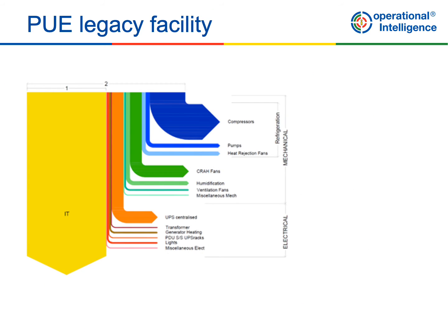PUE is a metric widely adopted in the industry to measure energy performance. So in this example, we're showing the PUE and the energy breakdown of a legacy facility. The ratio of total energy being used to the IT energy being used is 2, which means that for every 1 kilowatt we're using for our IT equipment, we have another 1 kilowatt in the supporting mechanical and electrical infrastructure, so in power distribution and cooling.